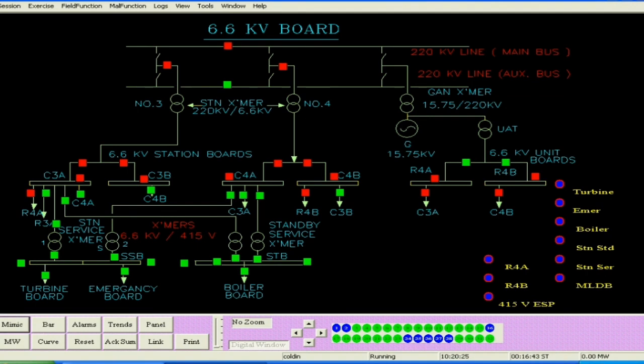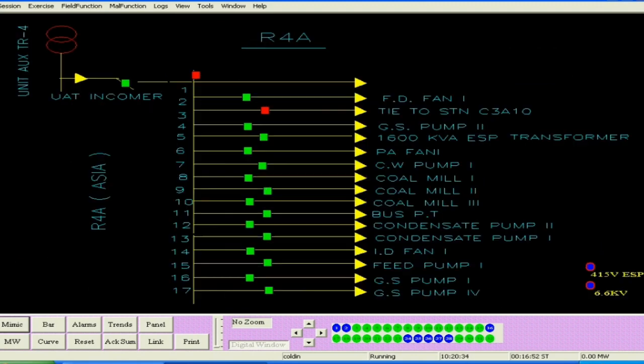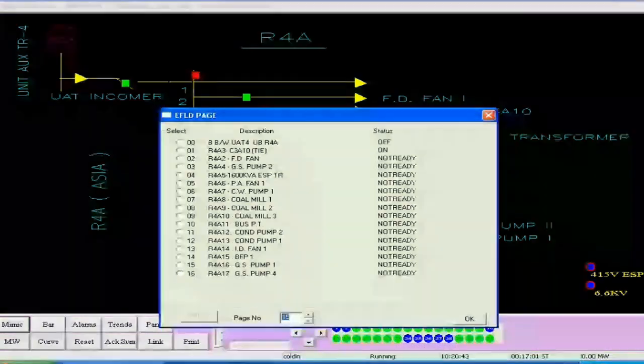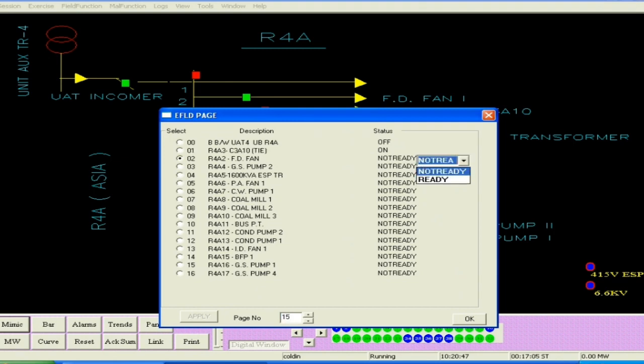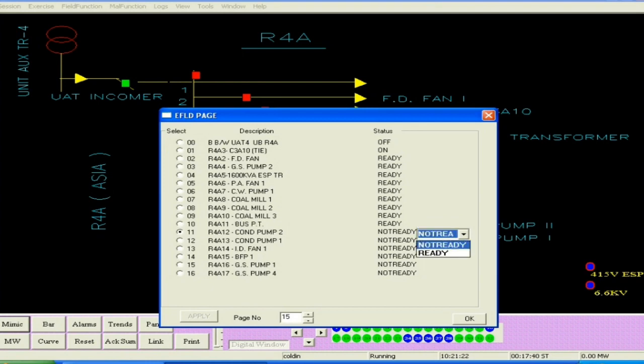Now we will make the breakers ready on the 6.6 kV board so that they can be operated from remote, means from the control room. So we go to the R4A board, and here you can see the R4A board mimic. You can go to page number 15, and from index number 2 to index number 16, we make the breakers ready for all the auxiliaries. That is FD fan, GS pump, then ESP transformer, PA fan, CW pump, coal mills, then the bus PT, condensate pump, ID fan. One BFP is there on R4A, and two GS pumps, pump number 1 and pump number 4. So all these breakers will be made ready so that they can be operated from the remote control room.